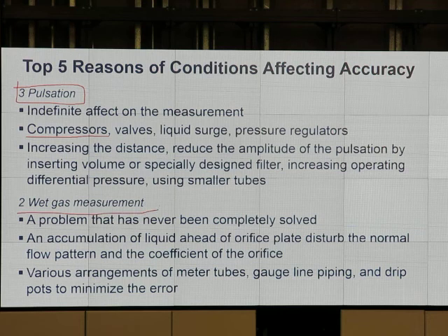Wet gas. Orifice plate is for single phase. Okay, just gas. Most of the time it's for gas. If it's for liquid, you will use... I think it can be done, but all the coefficients and correction factors will be completely different. Different derivation. But it's mainly used for gas, and it has to be dry. If the gas has some droplets, it causes inaccuracy. So this means the separator and mist extractor must remove all of those already. Otherwise, the orifice plate flow meter doesn't work.